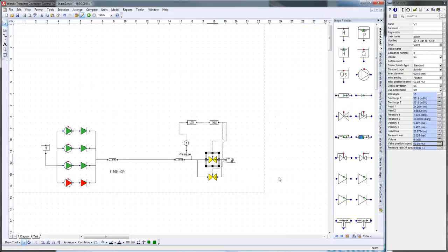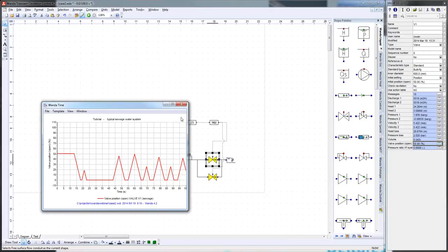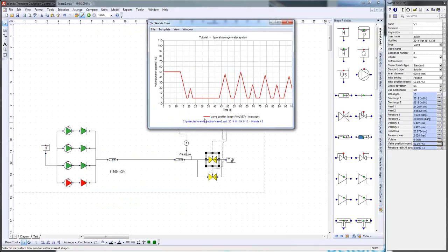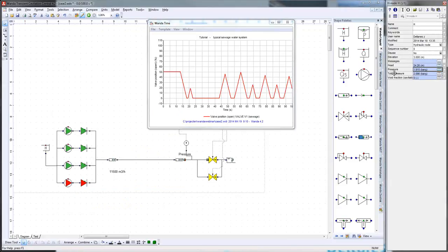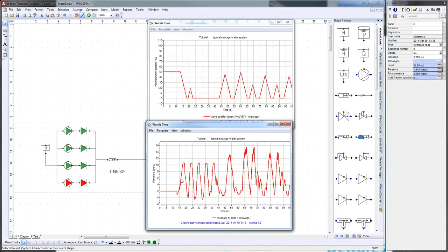So let's have a look at what's happening. Looking at the valve position here, we see an interesting behavior. The pump trips. Looking at the pressure below, you see the pressure is dropping - at that moment the valve starts closing. It's closed. But then the pressure rises, and if the pressure is five seconds above 1.5 bar, then the valve starts opening again. But when the valve is opening, the pressure is dropping again. At a certain moment it drops below one bar, so it starts closing again. It's basically not the behavior you want in your system - it's too dynamical, you want it more slowly.